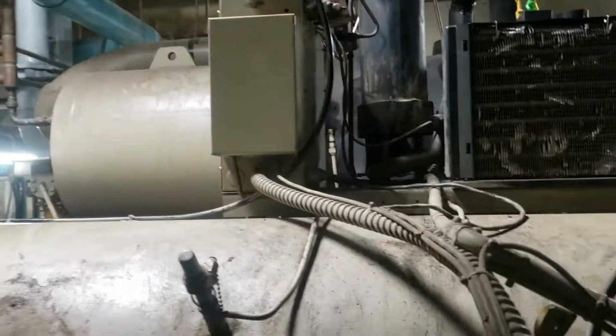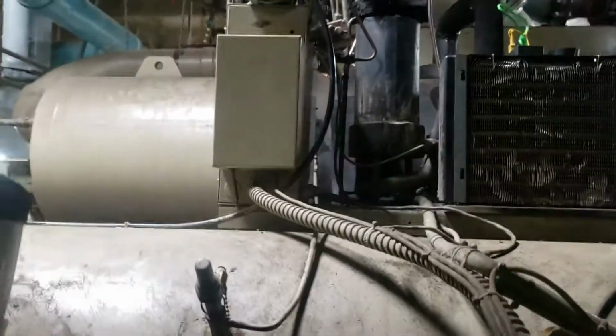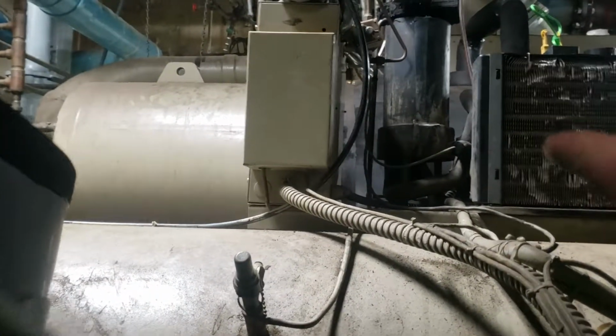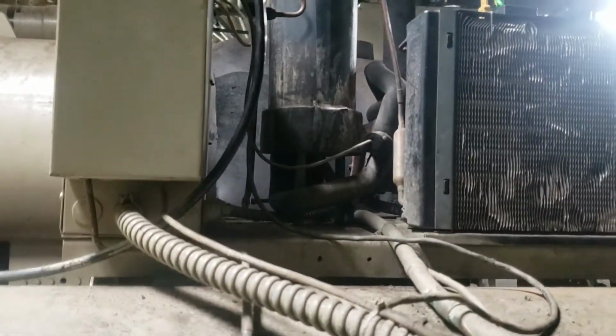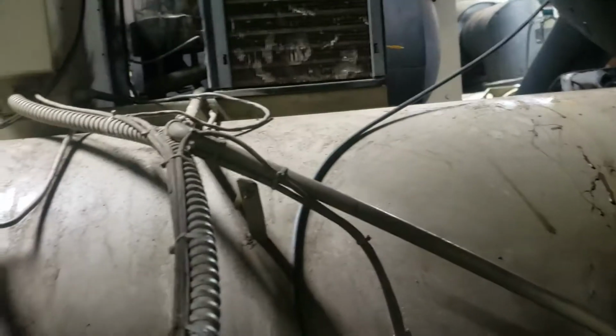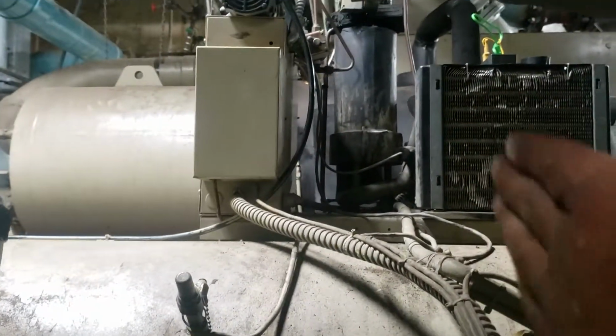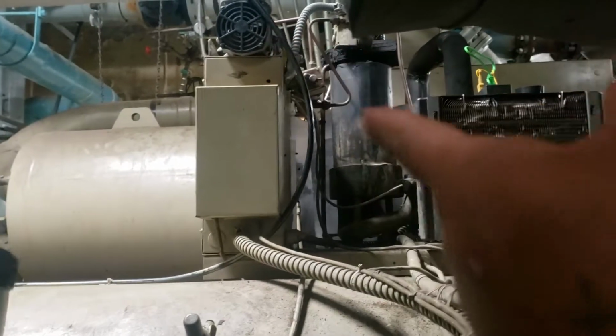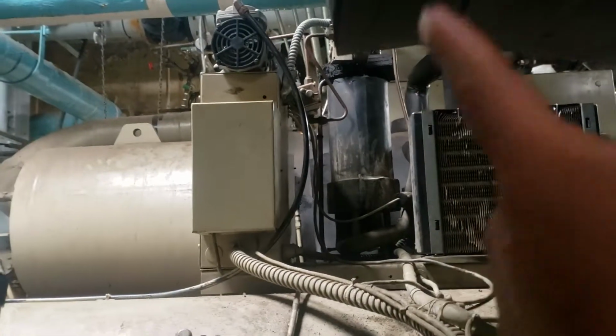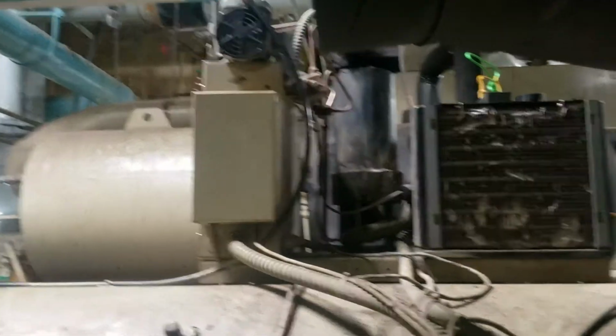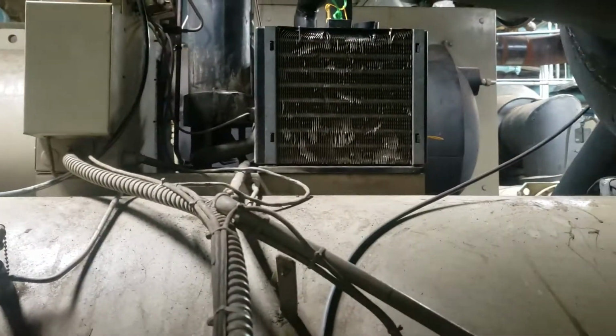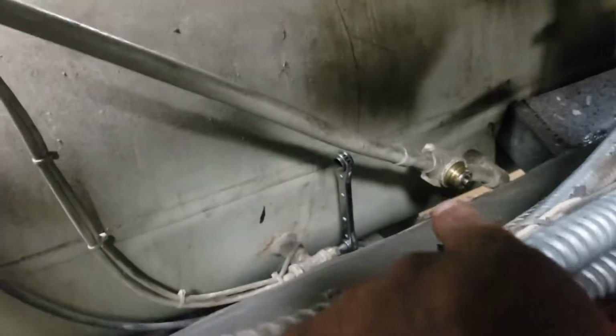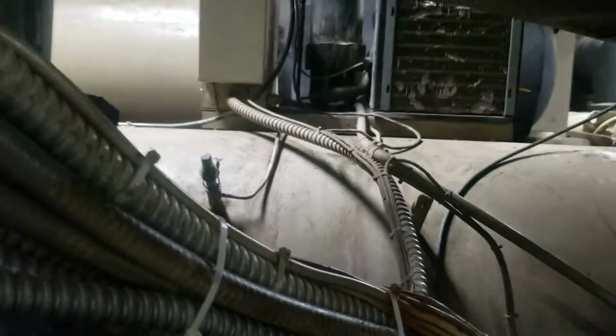So eventually it's going to enable the pump to start again. That's how you know if your sensor is good. See that sensor on that suction line? That's how you test to see if it's working. Once you shut them off and the suction temp drops low enough, or below 18, that pump should come on. And if it does, it should keep running until you open these valves back up. Once you open these valves back up, your suction temp will start to climb again.